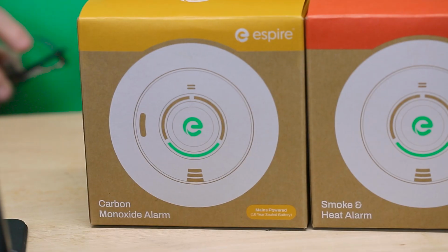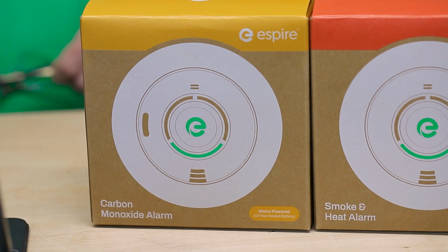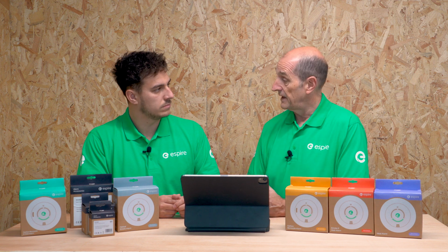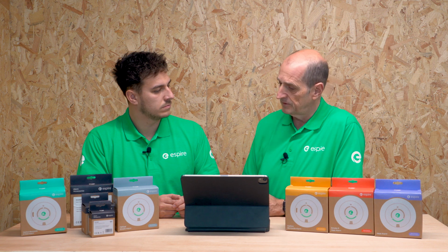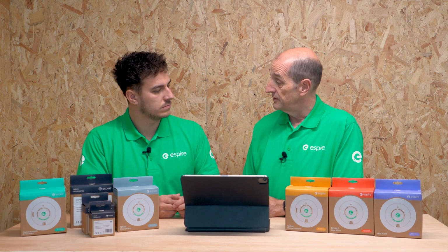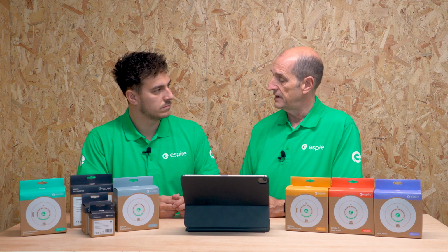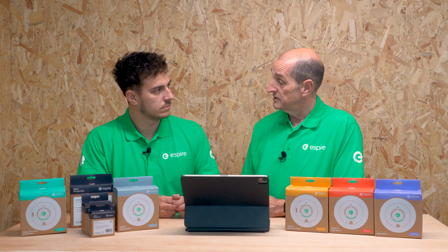Okay. There are two ways in which we might use a CO detector. We may use a CO detector to detect the products of combustion from a fire, but we would need to have a detector that is to a slightly different standard. However, when we want to look at a device that would detect the products of incomplete combustion from perhaps a gas fire, a gas cooker, a coal fire, something like that, and the buildup of carbon monoxide, then a CO detector to EN 50291 is a perfectly good thing. And they can be interconnected to a fire detection and fire alarm system.